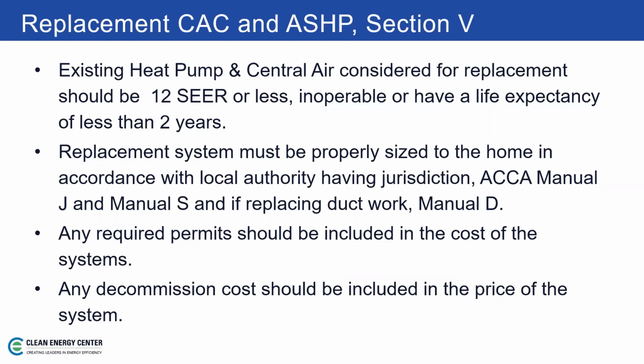System should be properly sized to the home in accordance with the local authority having jurisdiction, and that should be done according to ACCA Manual J, and also utilizing Manual S, which is the ACCA manual for selecting those combinations of equipment. And if you're replacing ductwork, if you're going to get into that larger scale job, then Manual D would come into play as well.